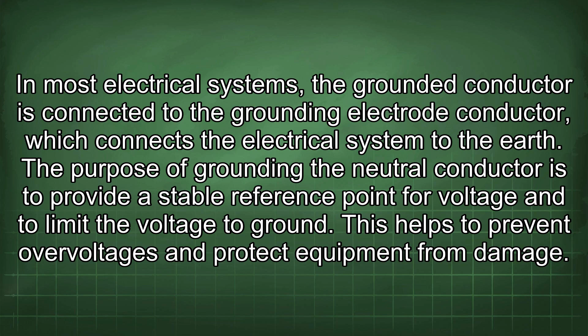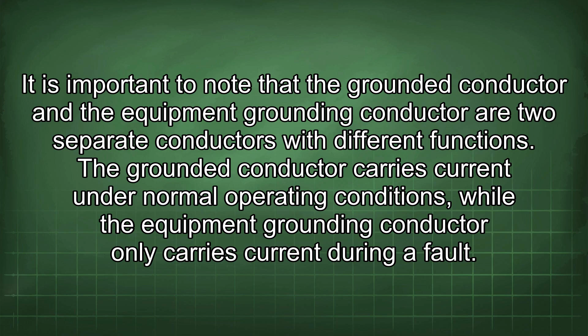It is important to note that the grounded conductor and the equipment grounding conductor are two separate conductors with different functions. The grounded conductor carries current under normal operating conditions, while the equipment grounding conductor only carries current during a fault. The two conductors should never be connected together except at the service entrance or at separately derived systems. Another important aspect of grounding is the concept of bonding.